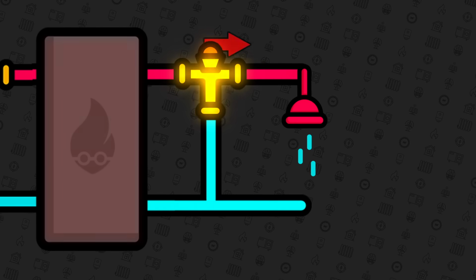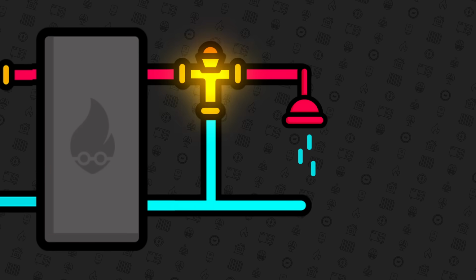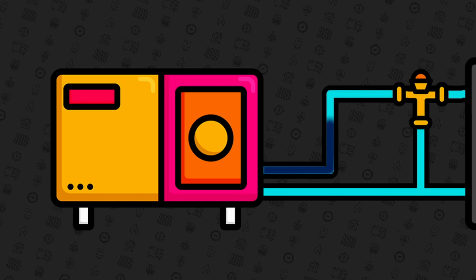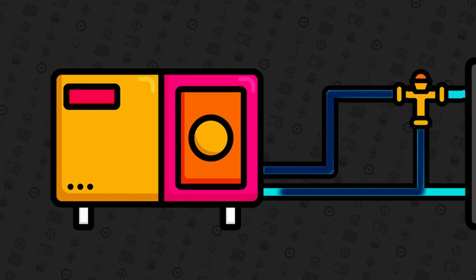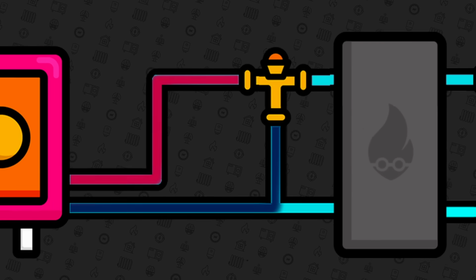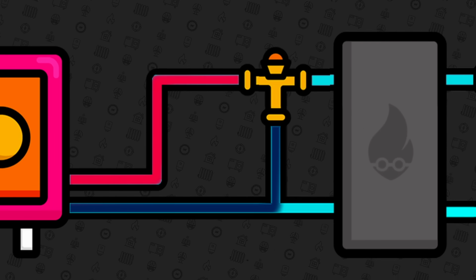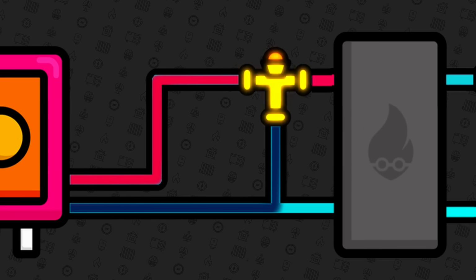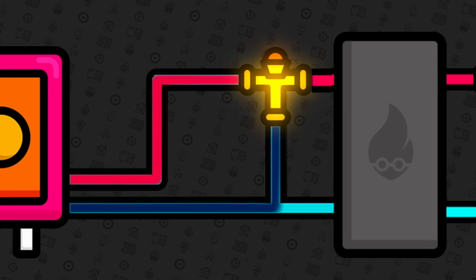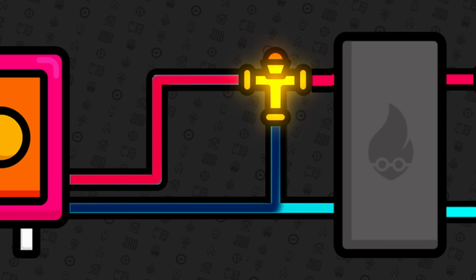At this point, it blends in with the cold to leave ready at shower temperature. On the other side of the heat exchanger, the heat from the heat pump arrives at this valve and then circulates back round until it gets hot enough. Once it reaches temperature, this valve opens and allows more heat into the plate heat exchanger.